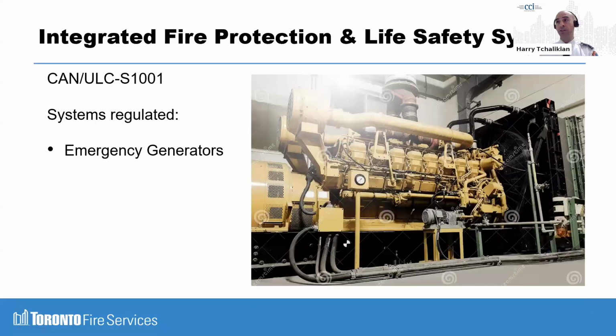Next, a relatively big one is emergency generators. So we were always already required to test our emergency generators as per CSA C282, the Emergency Generator Inspection Testing Maintenance Standard. This was already in the fire code. With integrated systems testing, there is a significantly higher level of testing that's involved here. In the CSA C282 standard, you monthly tested it by switching over a transfer switch, and it was just 30% rated capacity that you would be testing the output for. Annually, you required a 100% load test. So is it putting out the 100% output it's required in terms of emergency power?